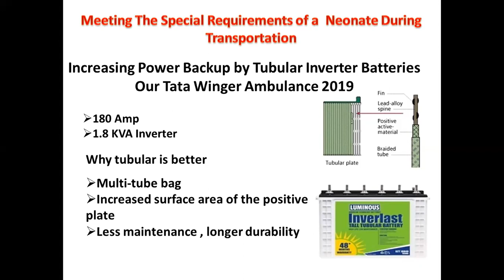So in the worst case scenario, there's a breakdown in the inverter supply. What happens then? Infusion pumps have a backup of 3 to 4 hours, so they will run for some time, and you can always adjust the drip rate as needed. But the worst thing that could happen is the incubator stopping, which would be very serious from the baby's point of view.